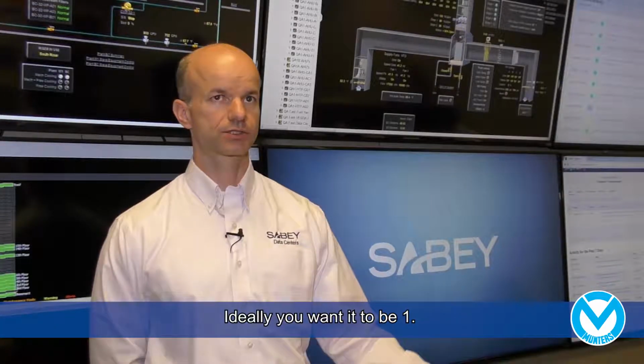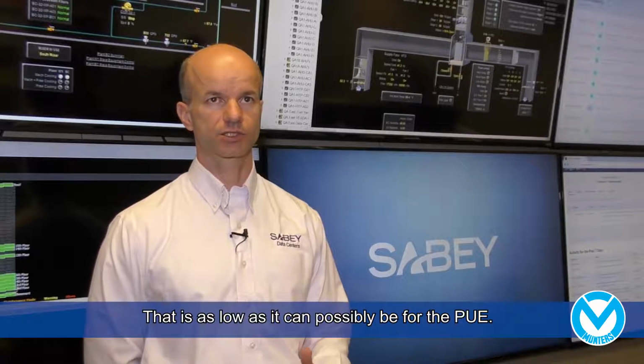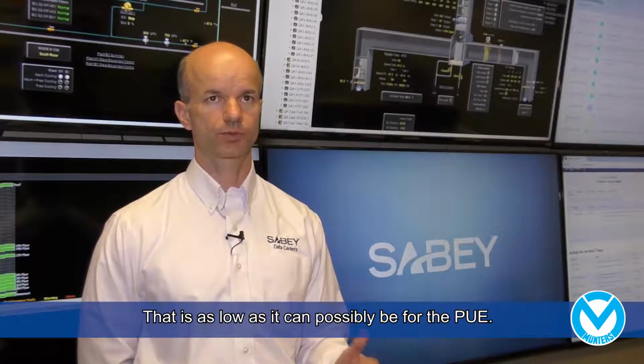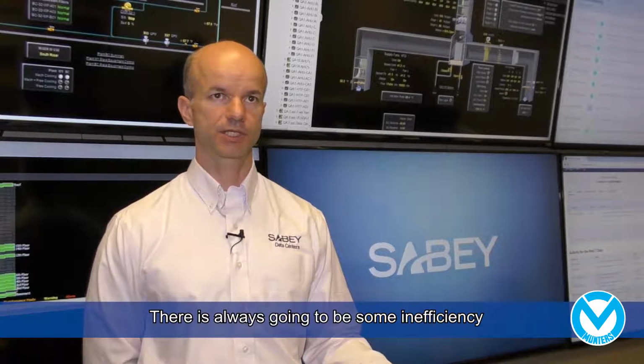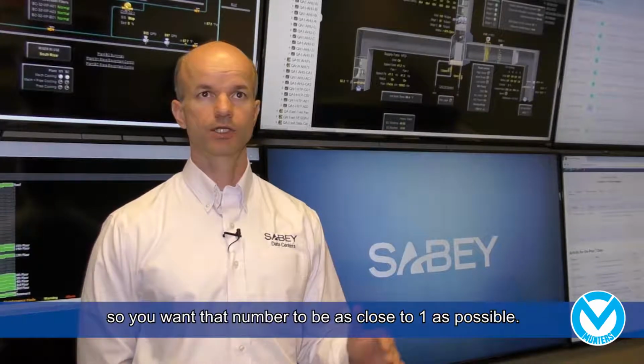Our average annual power utilization effectiveness in our most efficient facility here is 1.13. Ideally, you want it to be 1 - that's as low as it can possibly be for the PUE. There's always going to be some inefficiencies, so you want that number to be as close to 1 as possible. 1.13 is an excellent number for data centers.